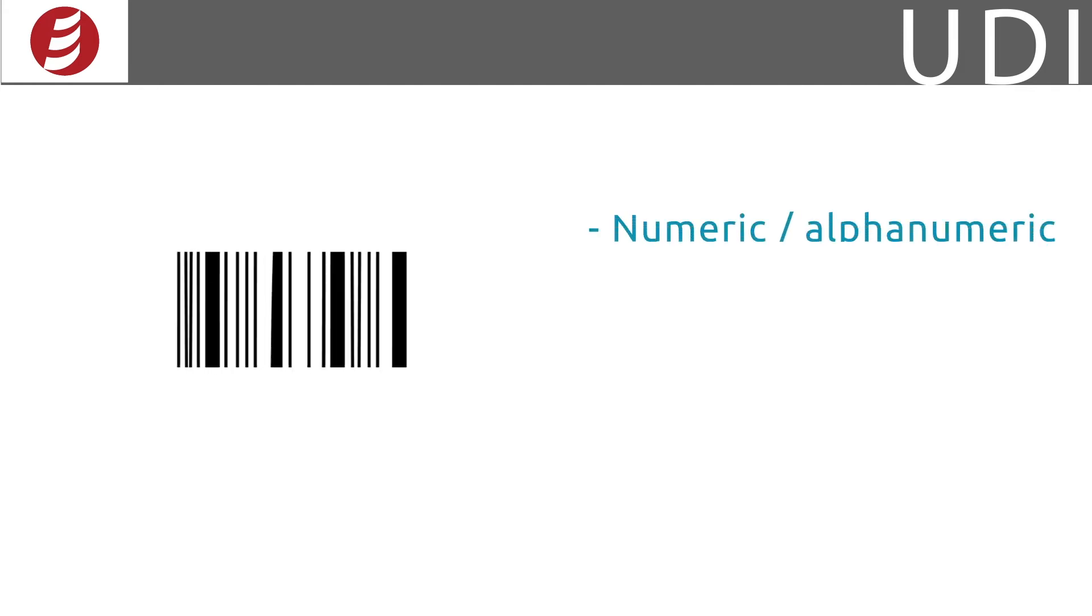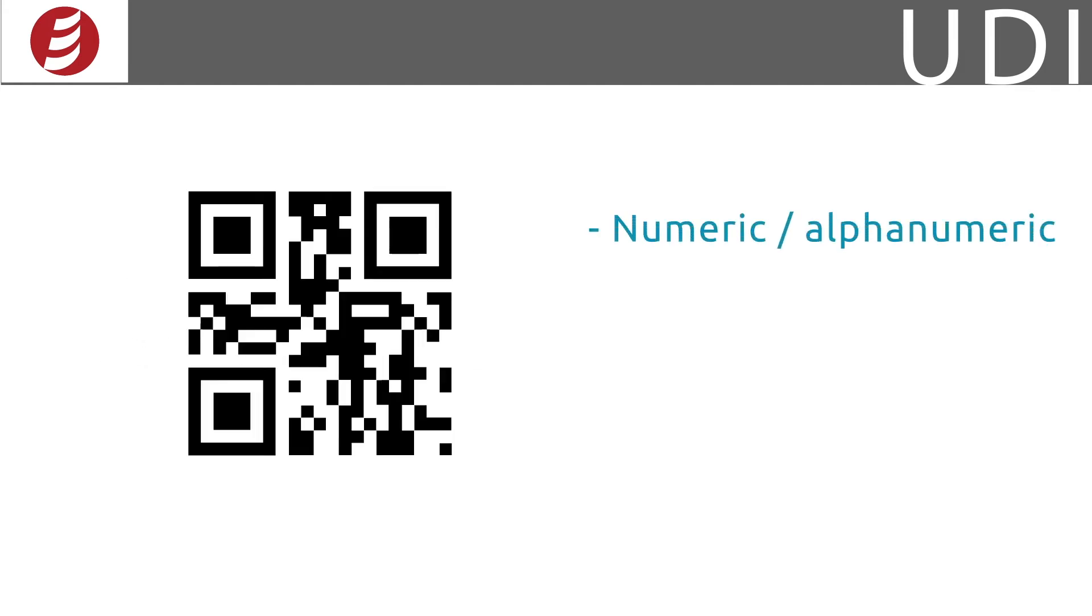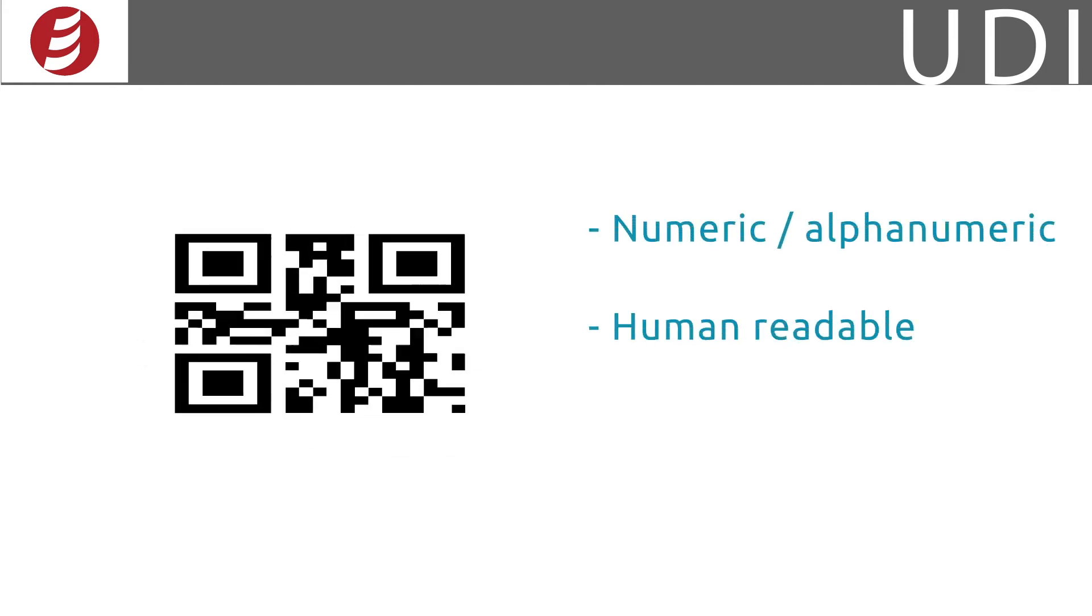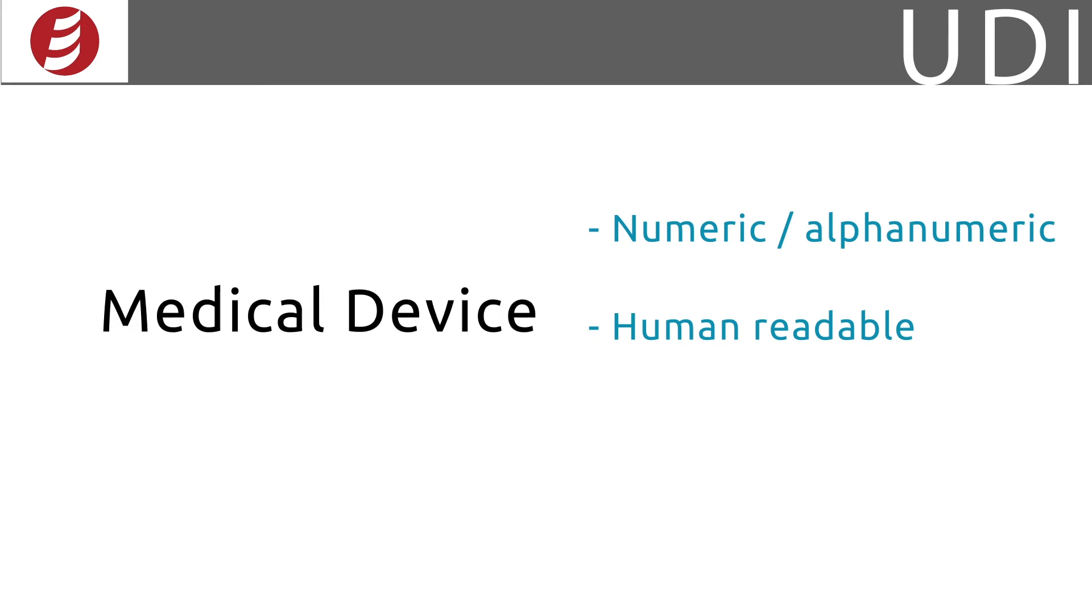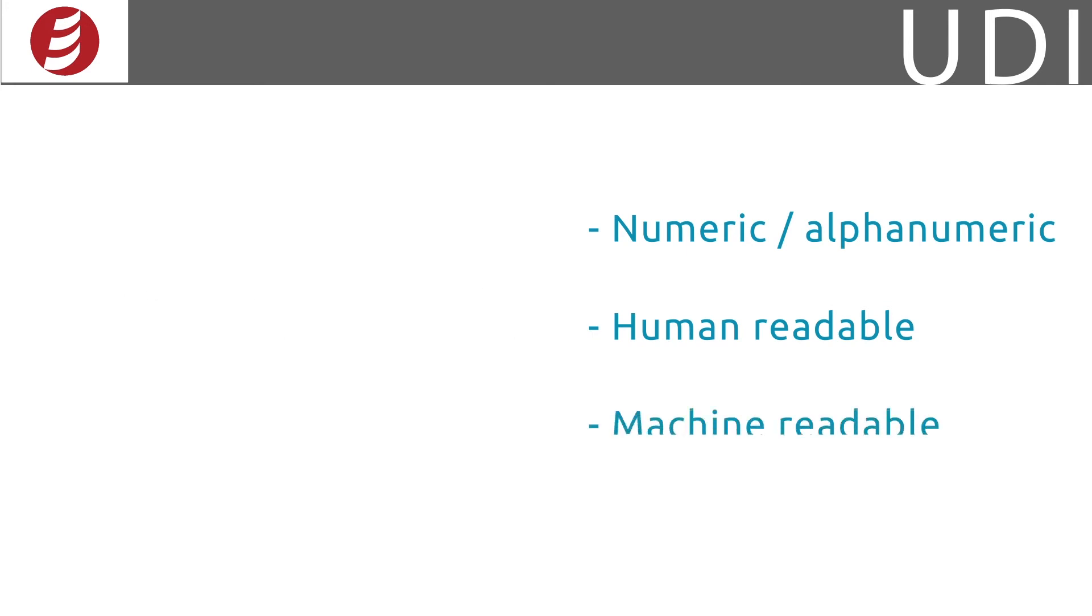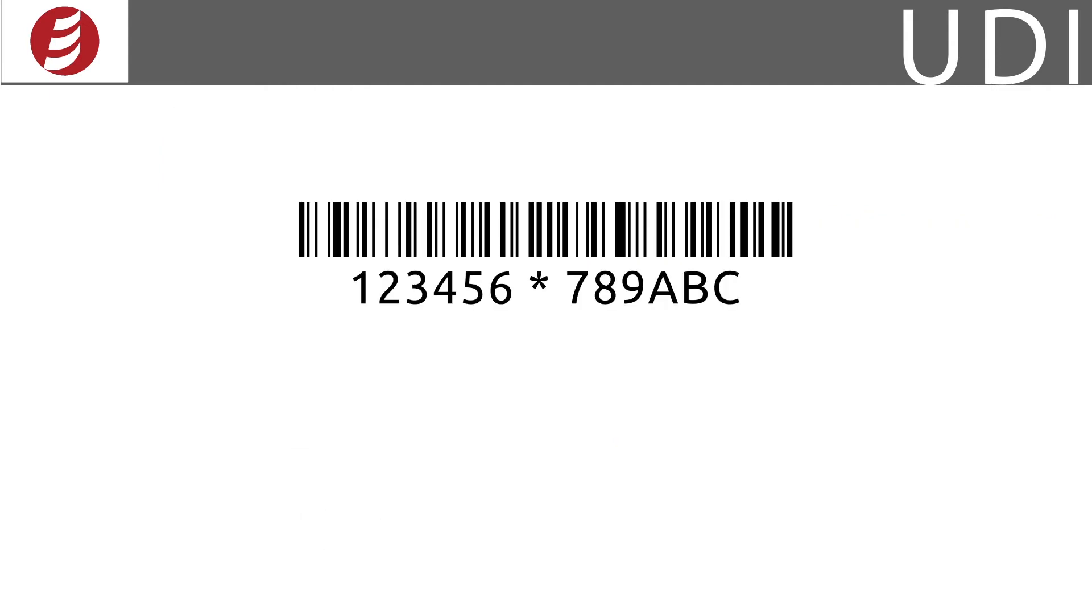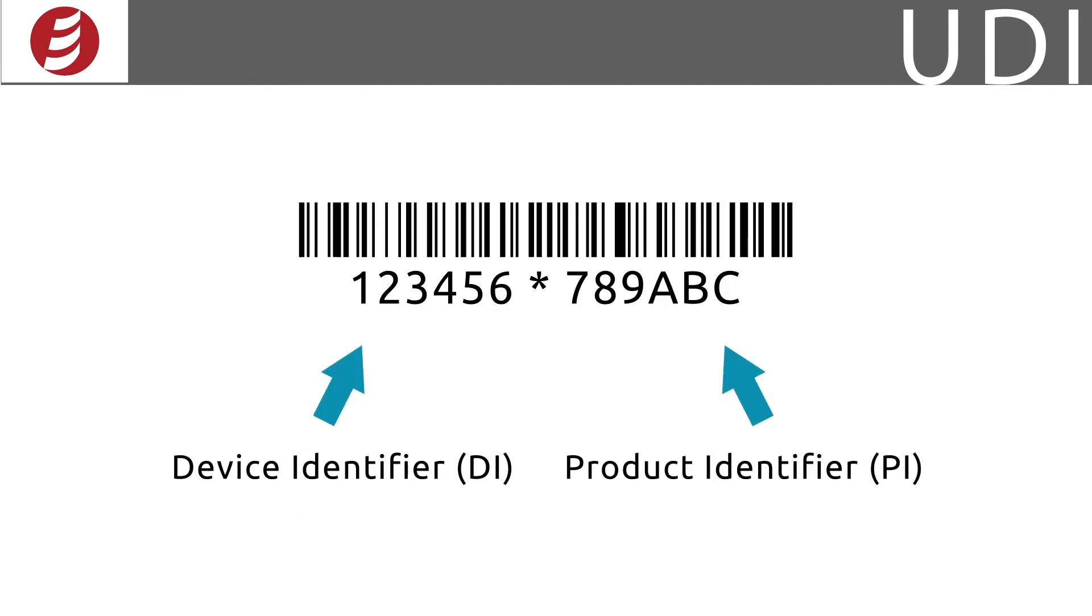The UDI can be numeric or alphanumeric. It must be displayed in human-readable, as in plain text, or machine-readable format, such as a barcode, RFID, or QR code. There are two parts to the UDI: the Device Identifier, and the Production Identifier.